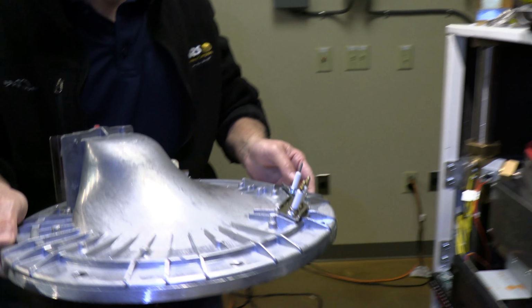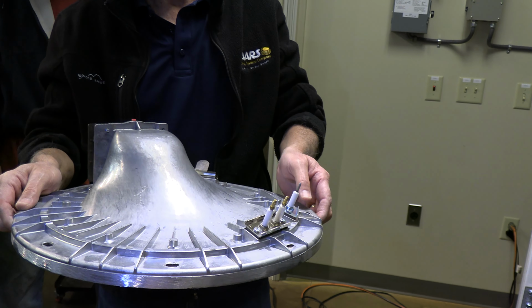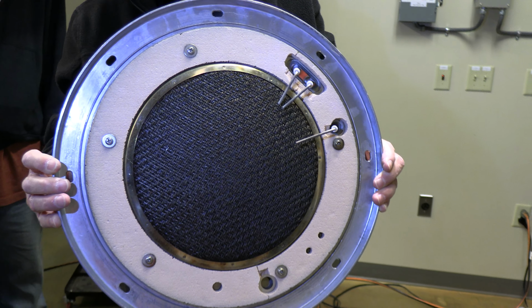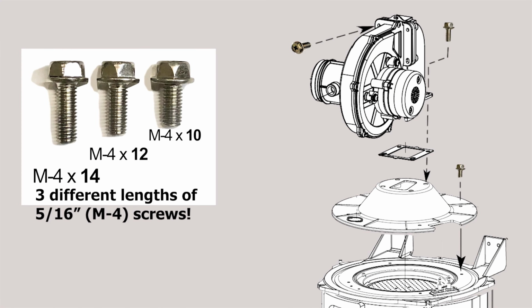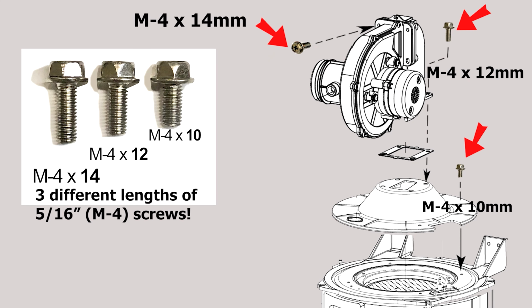and then the manifold. For the 199, it is possible to take the entire blower and elbow assembly out in one piece. And for the 301-399 model, the blower comes off first, then the manifold comes out with the burner and igniters in one assembly. Whichever model FT you are servicing, you must keep in mind that there are several different lengths and sizes of the screws. They are not all the same, so you must take note of this and keep track of where these different screws were used. Use separate bins if you must. This will save a lot of frustration in the reassembly.